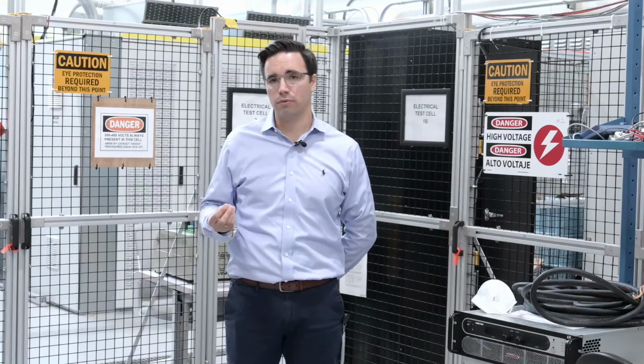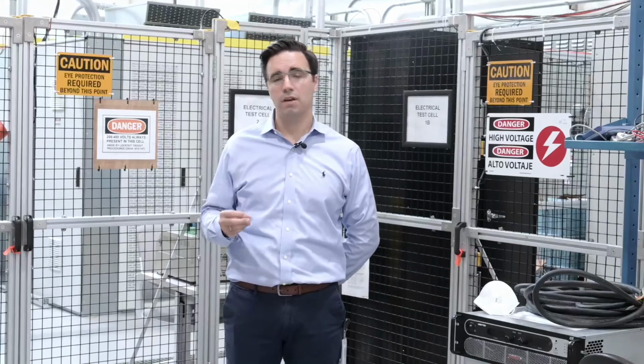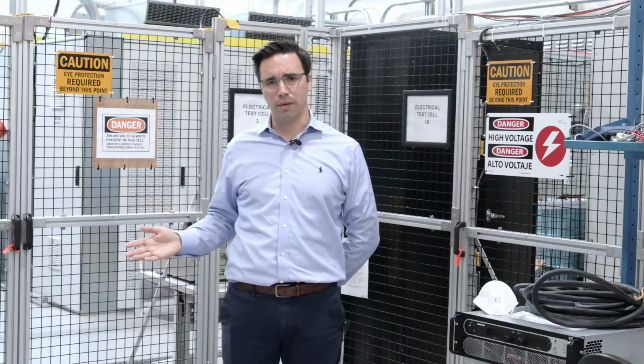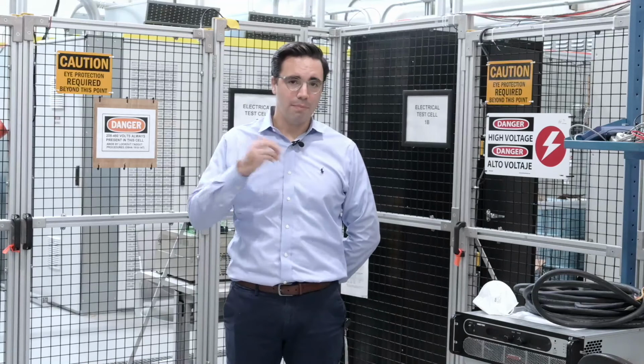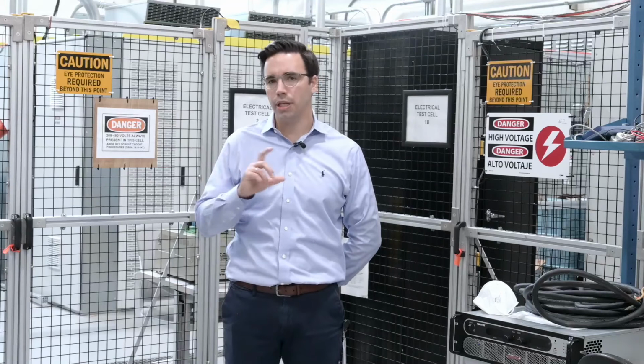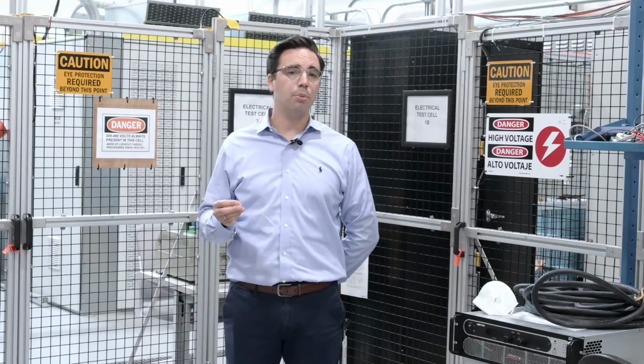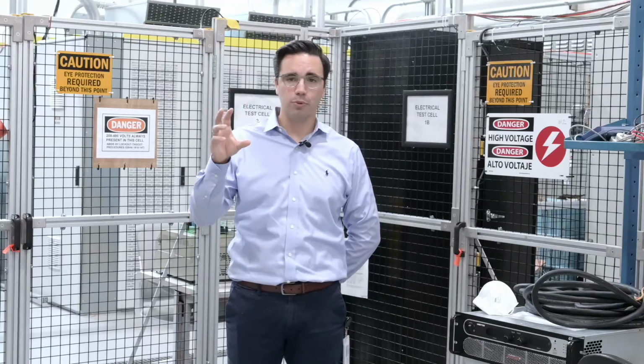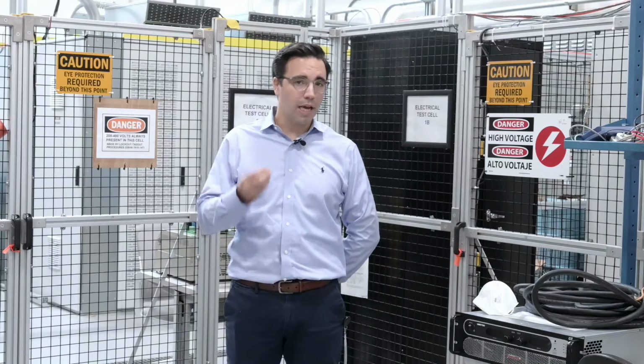The second option is a hybrid option. In this case, we have a solid-state breaker as a main breaker, and an electromechanical breaker downstream. In this case, we are able to protect the main rectifier, but there could be some open points when it comes to coordination between the solid-state breaker and the electromechanical breakers. The third option is a pure solid-state option. In this case, we have solid-state breakers upstream and solid-state breakers downstream. And in this case, we can provide protection to the system, protection to the power converters, and coordination across the whole system. Okay, thank you, Pietro, for your contribution.